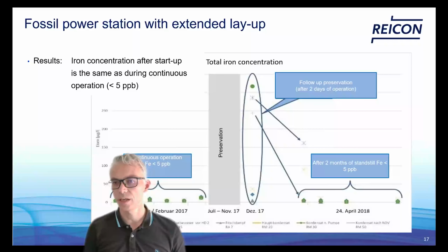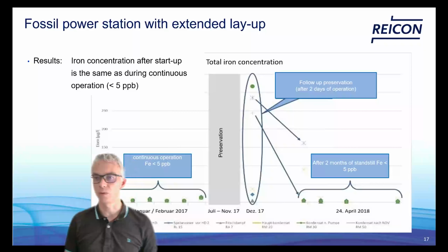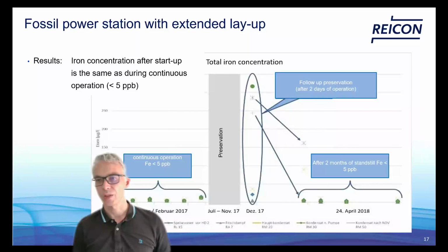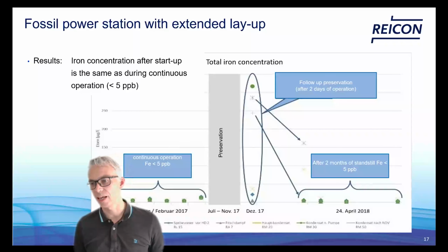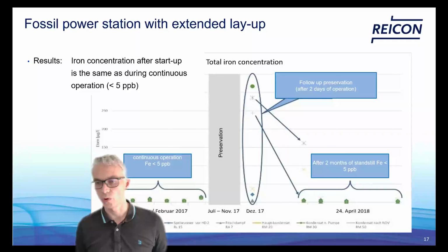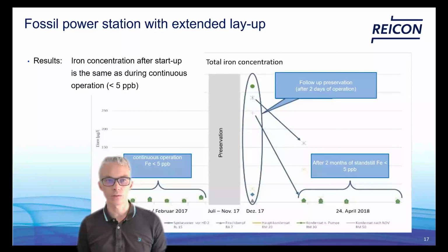And then you can see with the second recommissioning after a second treatment with ODA, the values go down. So we were again at 5 ppb at operations from a few hours a day for 2 or 3 days in a row. So a very good development here.